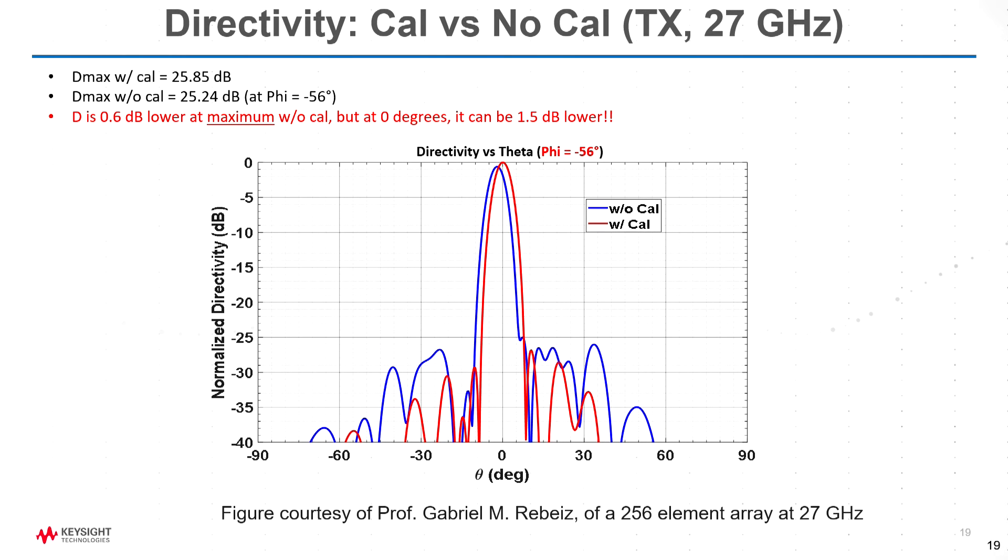Why does that matter? Well, the gain isn't changed so much by that, but the directivity or the direction of it is. So Professor Rebeiz kindly gave me this measurement of a different antenna. Shows in this case, the boresight apparent gain can change by about a dB and a half. The actual gain only changes by 0.6 dB when you calibrate it, but your pointing angle can be off as well. So you have to be quite careful with that.